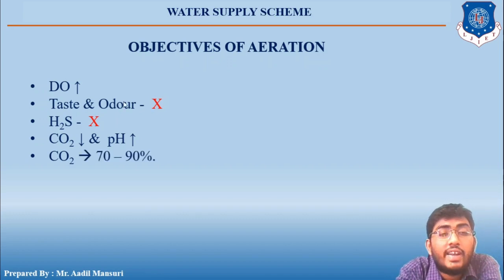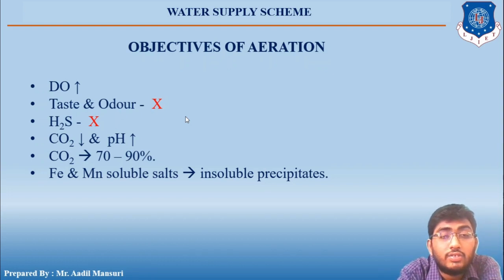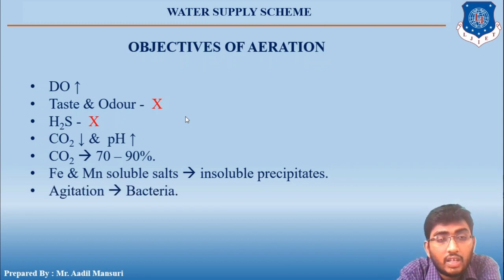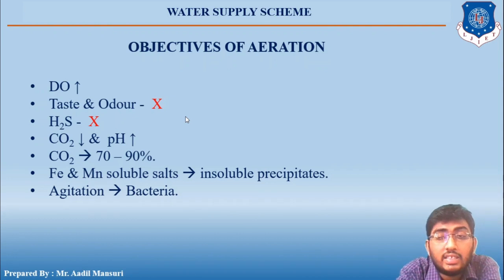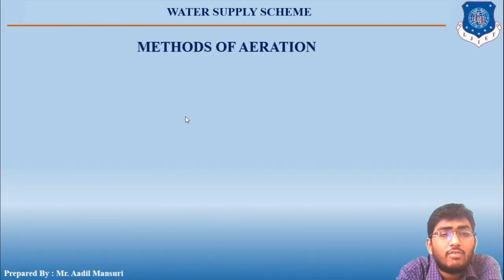Through the aeration process, carbon dioxide is removed up to 70 to 90 percent. Aeration is also responsible for converting soluble salts of iron and manganese into insoluble precipitates, which are then removed from the water. Additionally, constant agitation of water during aeration may kill bacteria to a certain extent.